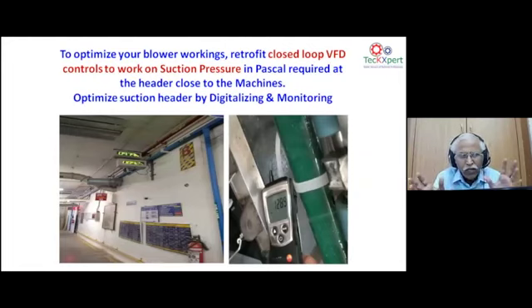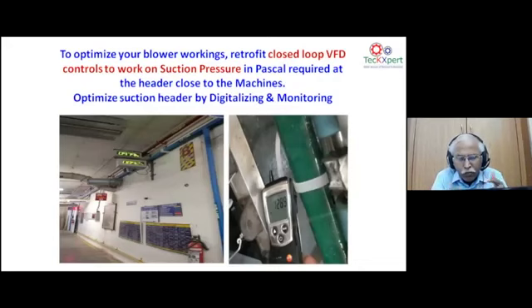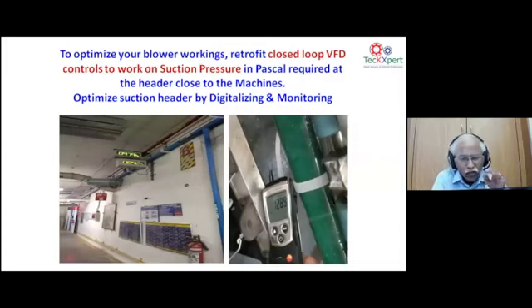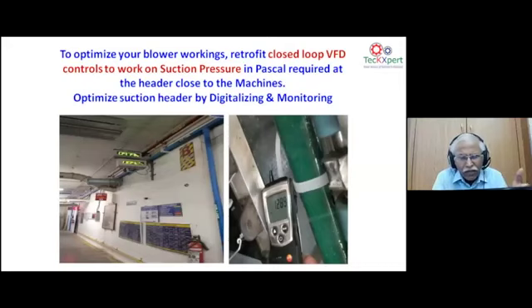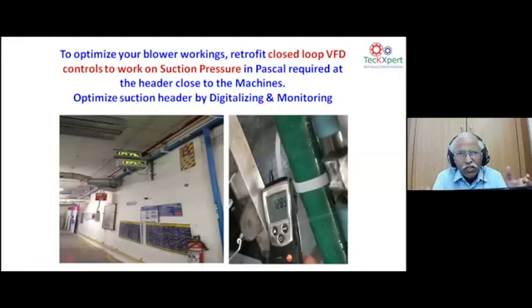The digital display monitors pascal variation caused by leakage and machine consumption changes. As the BEE principle states: monitor your energy to control it. Monitoring pascal has become critical. Beyond in-house instrumentation, handheld digital pascal meters (e.g., Testo brand, under ₹8,000) can accurately measure field pascal digitally — much easier than a U-tube manometer or ordinary tell-tale type manometer.